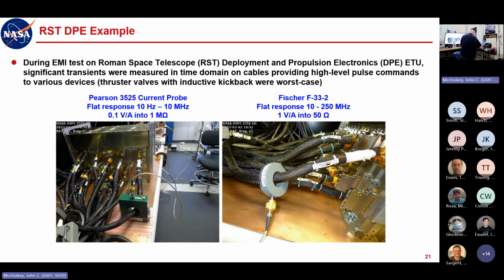If you use a current probe for a time domain measurement that has a response that's not flat, it's going to distort the waveform, and it's going to corrupt your ability to interpret what you're seeing. So the ideal thing to use in one of these tests would be one of those gun type current probes for an oscilloscope, because then your oscilloscope will just know it's this current probe, do the conversion for you, and display the current directly on the scope in amps or milliamps or whatever scale you're on. That's ideal. We didn't have one for this test, but if you have one of those, that's always your go-to device for time domain measurement.